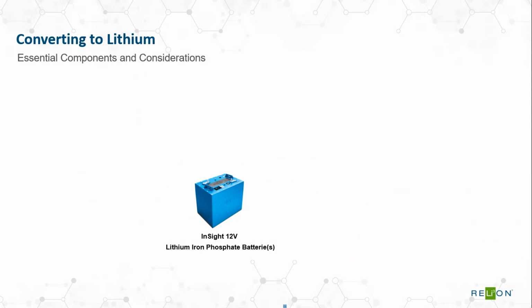So first off, we start with our Insight battery, and we begin with the battery monitor. Remember, earlier in the presentation, I talked about how the voltage characteristics of lithium are much higher. In my coach, when I put lithium in it and hadn't changed out my monitor yet, that gauge — because lithium runs well above 13 volts most of the time through most of its charge cycle, or down to 12 volts out to 90% depth of discharge — you're probably never going to see that on your lead acid battery monitor.